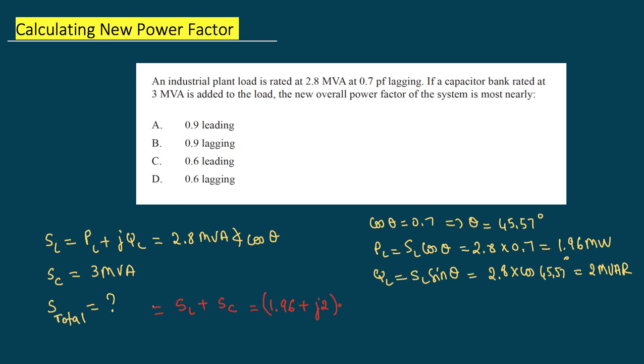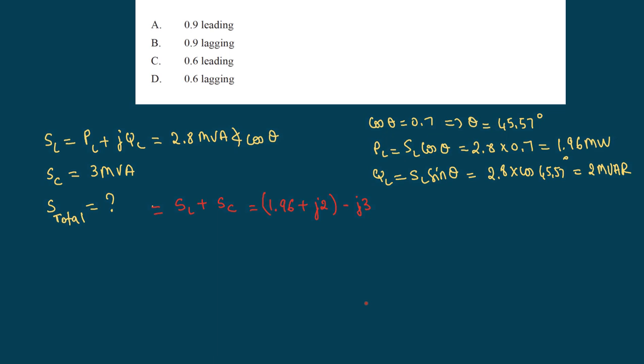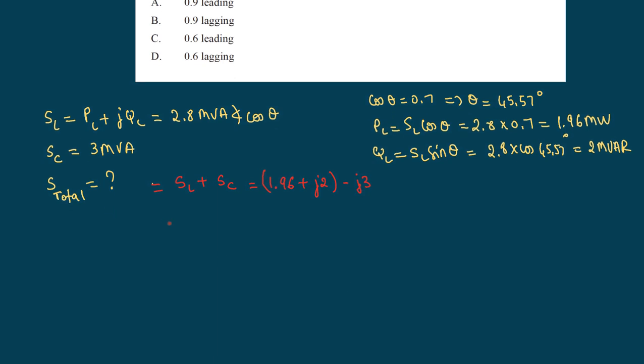And everything is in mega, so this is megawatts, MVAR, and MVAR, so we are good with units. We don't have to convert anything. And so this is my S_total. So now S_total is 1.96 minus j1. So this is my total system MVA.